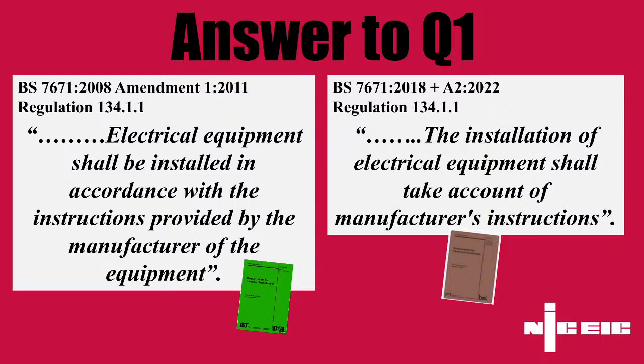And it changed the wording from "electrical equipment shall be installed in accordance with the provided manufacturer's instructions" to the fact that we should take account of the instructions as well. So from Amendment 3 of the 17th edition onwards, it's actually taken into account the instructions. So no blindly following the instructions. Yeah, absolutely.